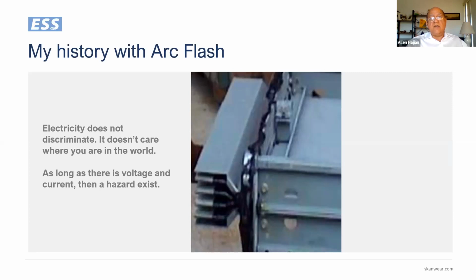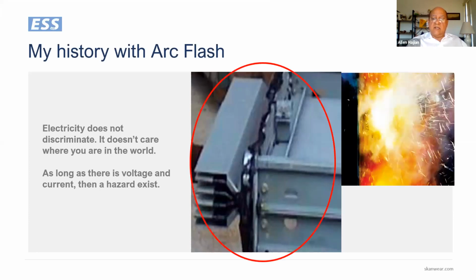When he tried to do the phase rotation, he experienced an arc flash. Unfortunately for him, this arc flash, if you're familiar with how arc flash is measured, in calories per centimeter square, was 160 calories per centimeter square. And it burned the clothing off of him. He was on a ladder, and he climbed down the ladder and laid on the ground, his flesh on fire. They put the fire out, and he sat up and said, "I'm burned pretty bad, aren't I?" And they said, "Just lay down, the ambulance is on the way."